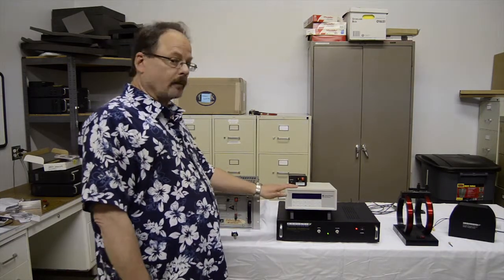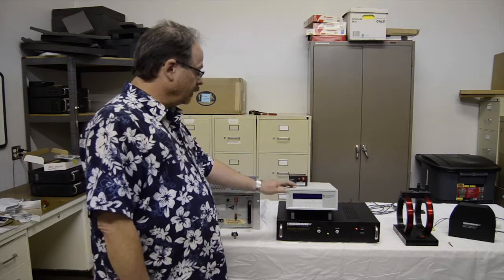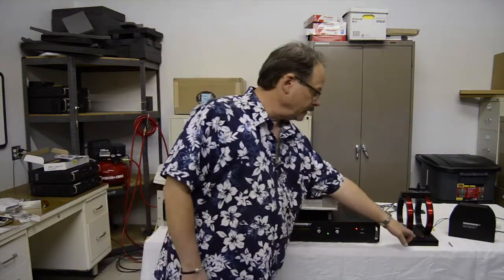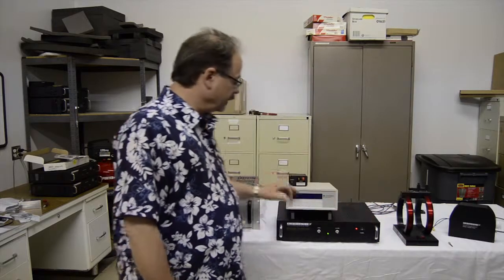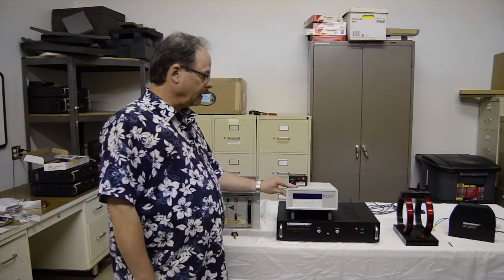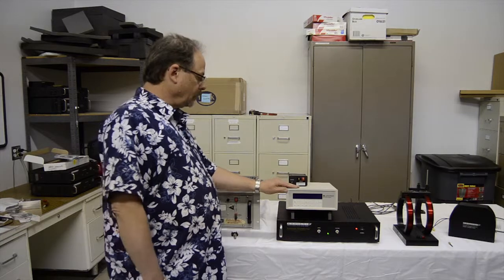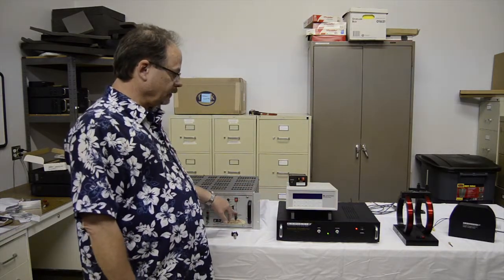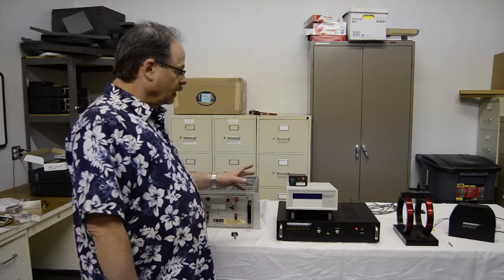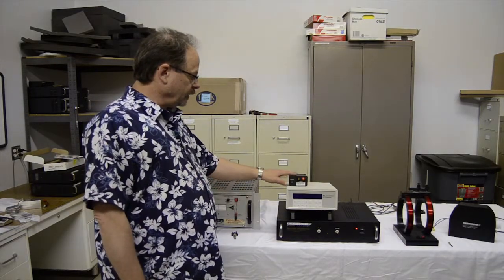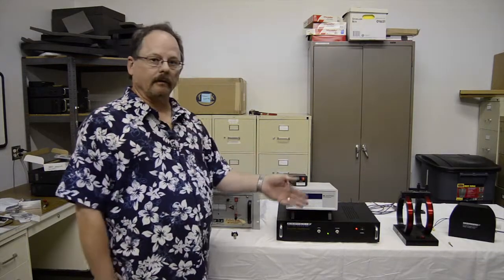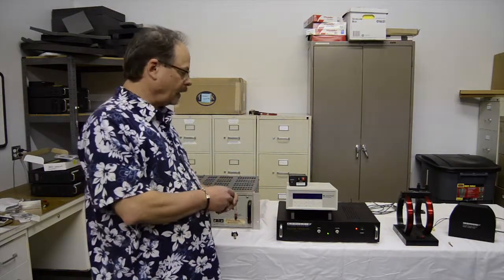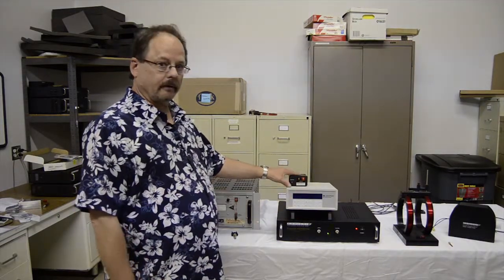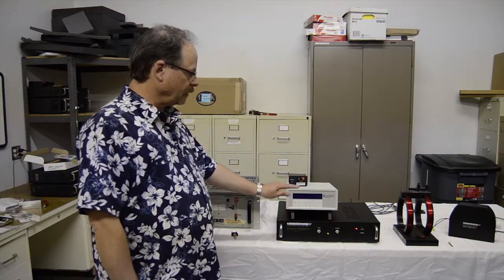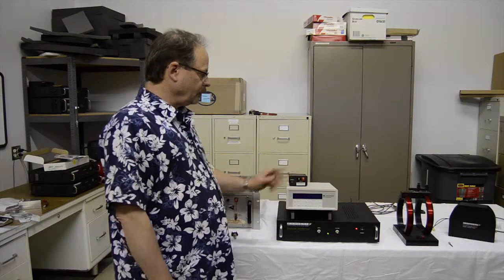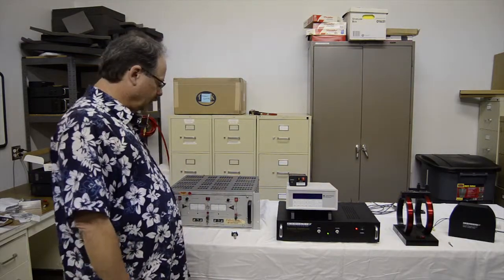So we're going to start with a calibration experiment in which we're going to measure the current into the Helmholtz coil and relate it directly to the field that we measure over a series of stepped currents induced by step voltages. What that's going to do is allow us to build a confidence that by knowing the current in, we can accurately predict the field out, and then we can measure the current in during the actual measurement, remove the Gauss meter from the measurement, and still be able to accurately predict the field that we're applying.